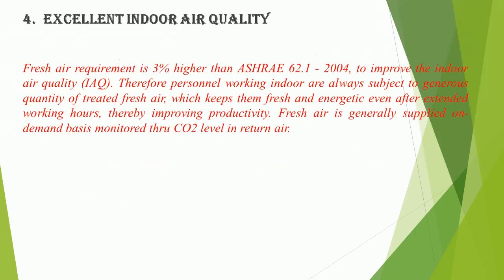Feature 4: Excellent indoor air quality (IAQ) — fresh air requirement is 3% higher than ASHRAE 62.1-2004 to improve indoor air quality. Personnel working indoors are always subject to a generous quantity of treated fresh air, which keeps them fresh and energetic even after extended working hours, thereby improving productivity. Fresh air is generally supplied on a demand basis, monitored through CO2 levels in return air.